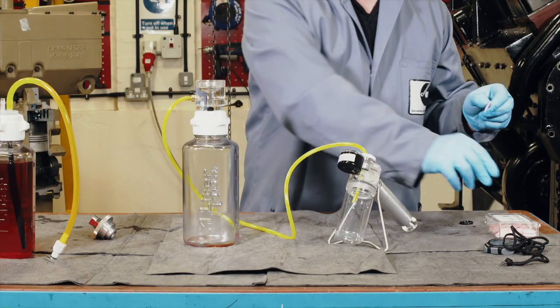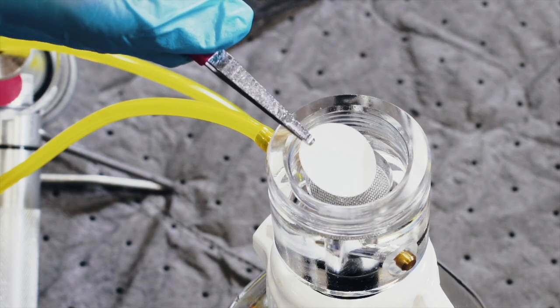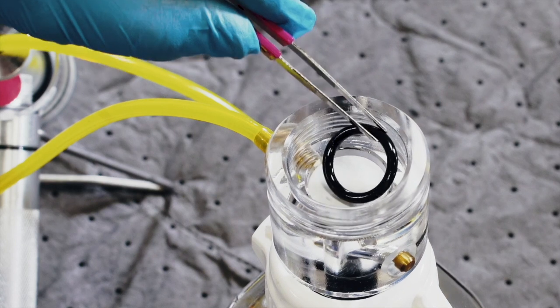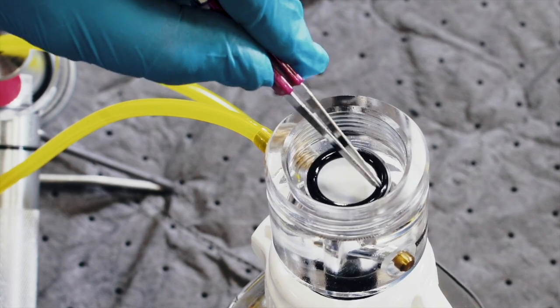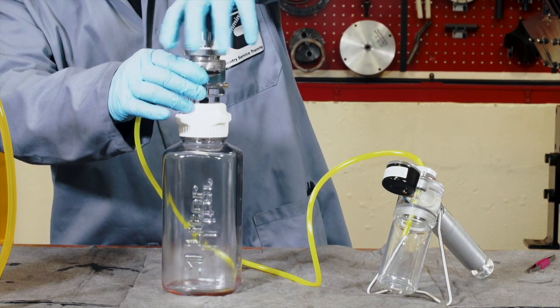Remove any coloured or separated sheets from the filter media and then carefully place the media with the grooved side facing the metal screen. Fit the small diameter o-ring on the top of the filter media and then tighten the siphon adapter securely in place.